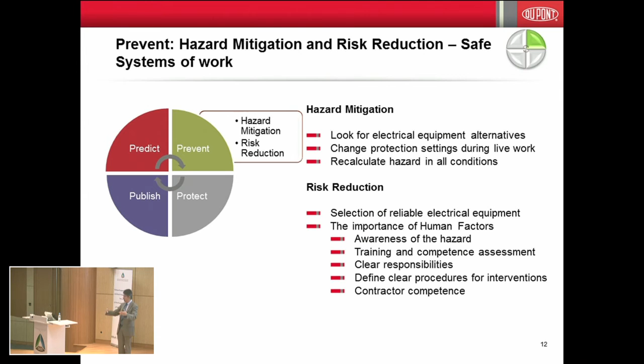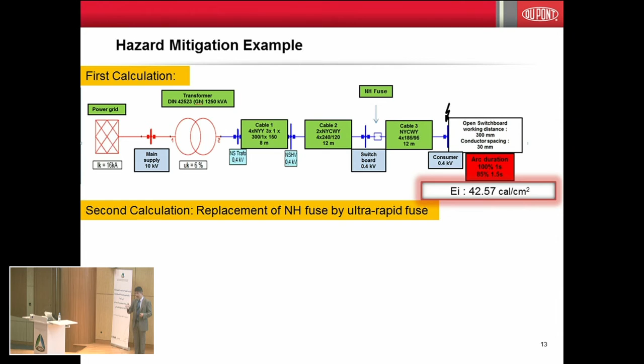We made a new simulation. In this new simulation we replaced the fuse. Here, as you can see, you have a fuse. A fuse is a system that helps disconnect and shut down the current and limit the hazard. The time of connection, if you remember about the electrical arc flash, has two key parameters: the amount of current and the time and duration of that. So what's going to be important, if you cannot limit the current, is to limit the time, because shorter means less energy.